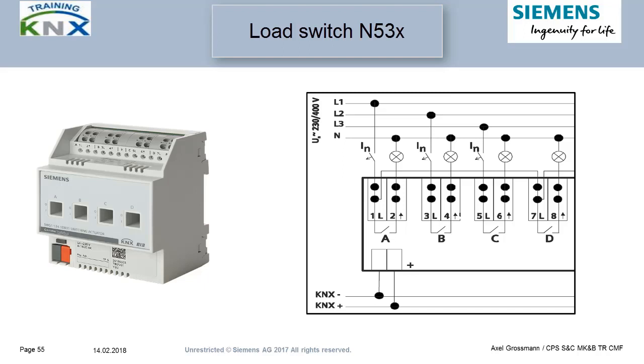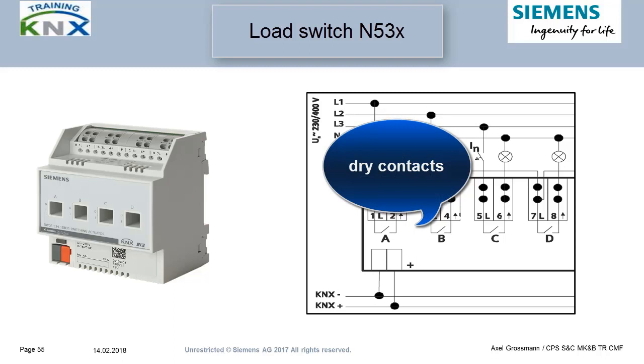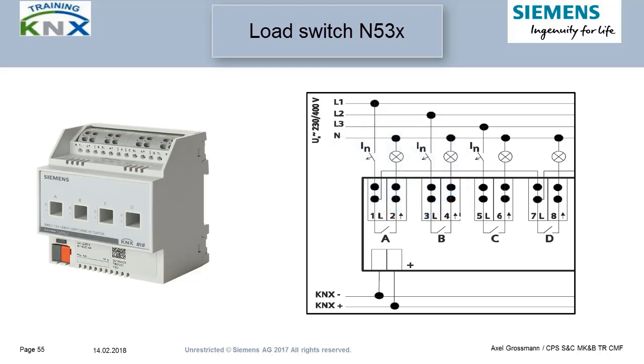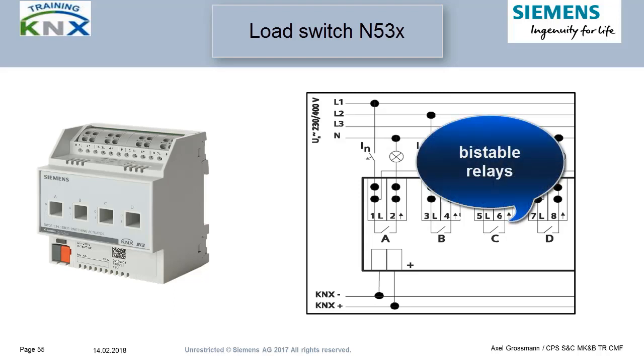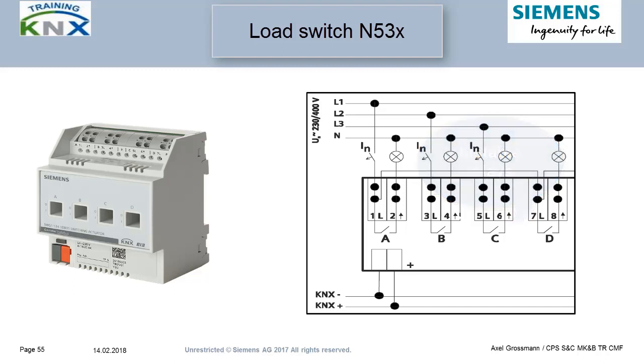A concrete example: the Siemens switching actuator N53X. The wiring diagram looks quite unspectacular, but you can recognize that the relays are independent from each other, so the actuator can also operate on different phases. It has bi-stable dry contacts, which can keep their condition in case of bus voltage or mains voltage failure. They can also be driven to a certain position in case of bus or mains voltage failure. A neutral conductor is not required — the device is controlled solely by the bus.